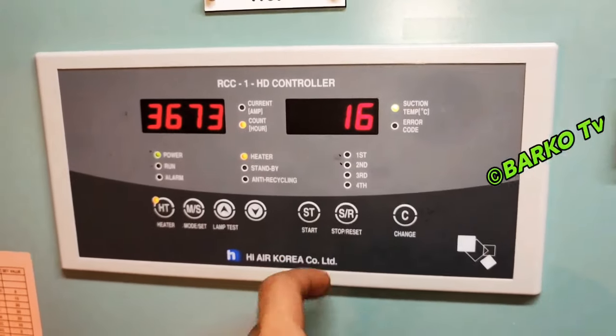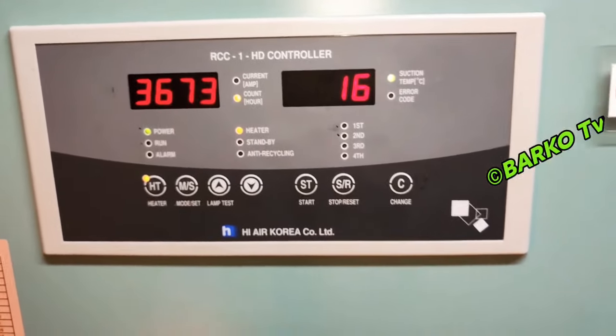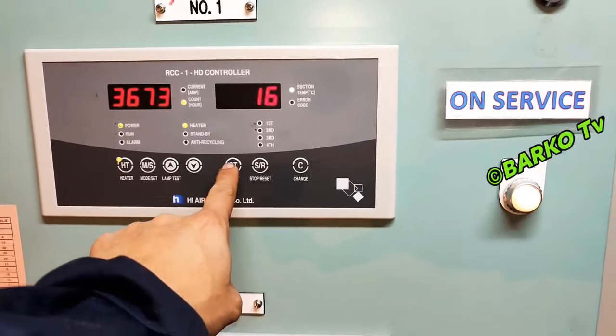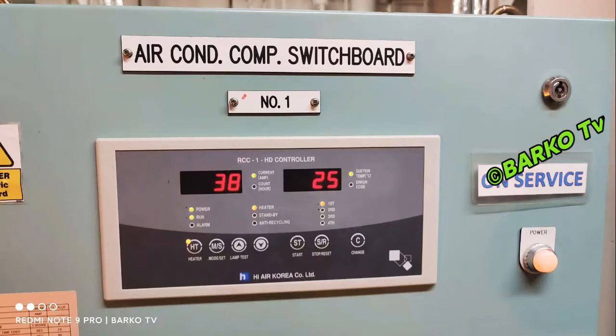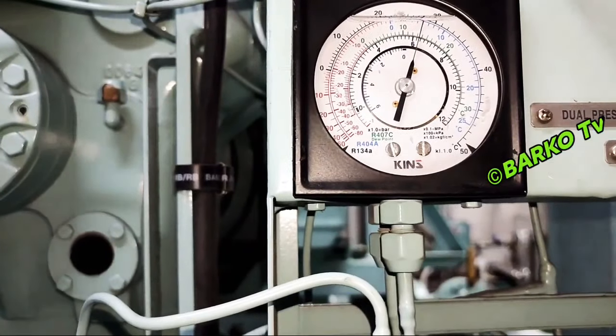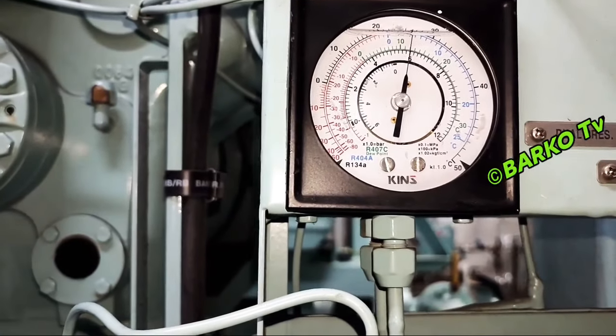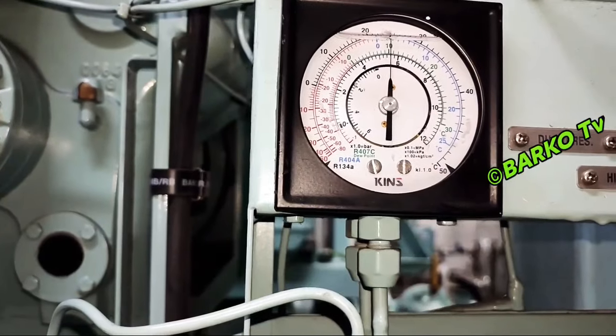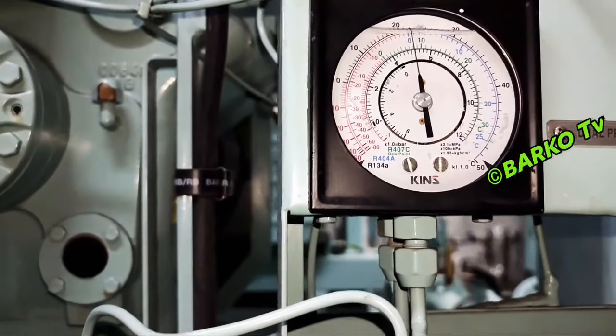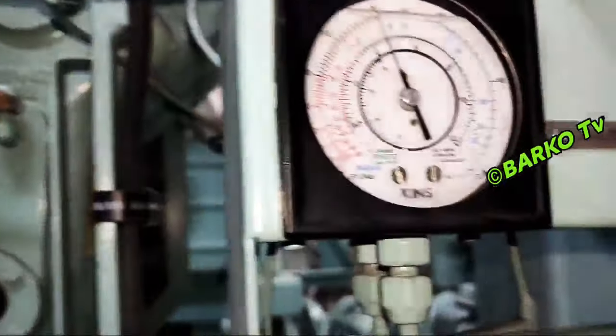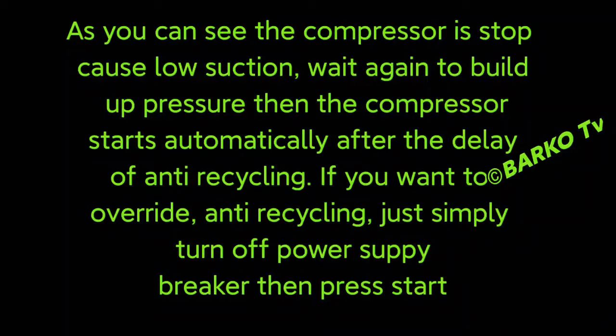Press stop and then start again. Press start. Okay, right now the compressor is running and starts to activate low suction. Just wait until low suction is triggered. The compressor automatically turns off and then the anti-recycling time is activated, but you need to wait until the pressure rises up. And then to reset the anti-recycling time, you need to turn off the control again and then press start.